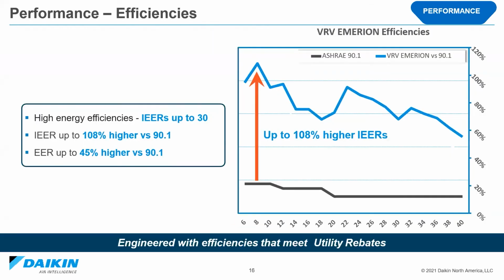All the advancements in the new line have allowed for industry-leading full load and part load efficiencies. So right now, the EERs have been moved up to 30, which is about 100% higher versus 90.1. In addition, the full load efficiency ratings have gone up. So they're now up to 45% higher versus 90.1. It's funny, I remember how impressed we were when we saw IEERs up to 23 years ago.